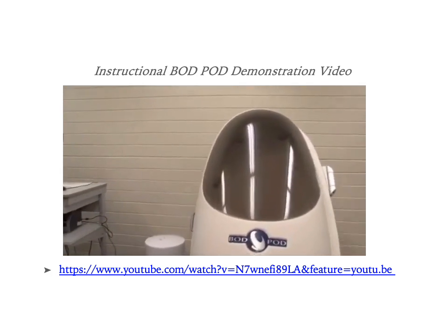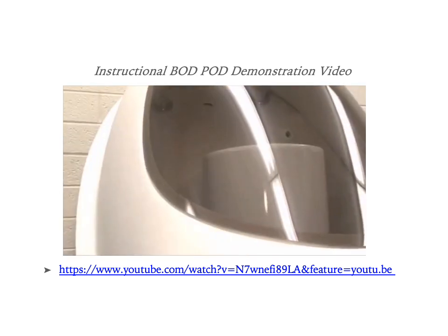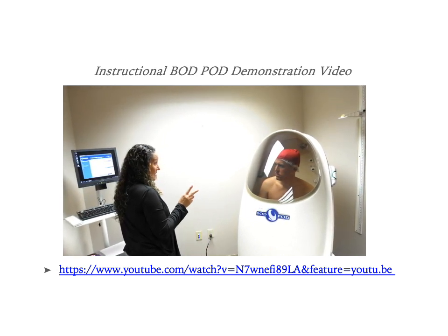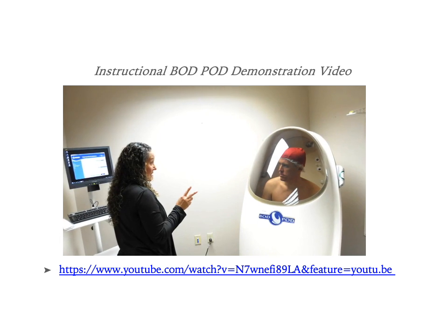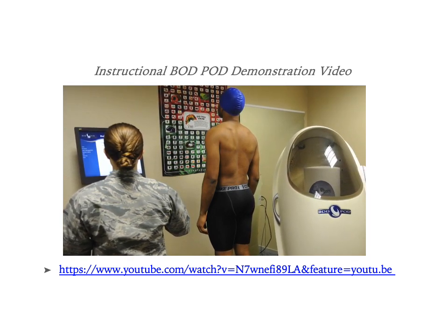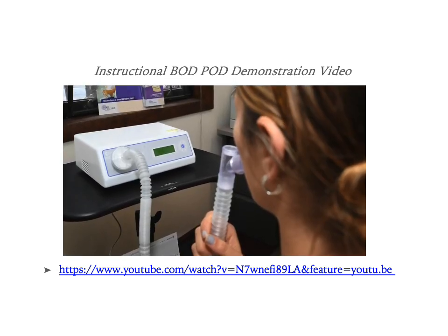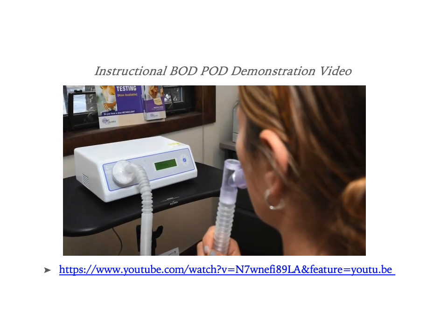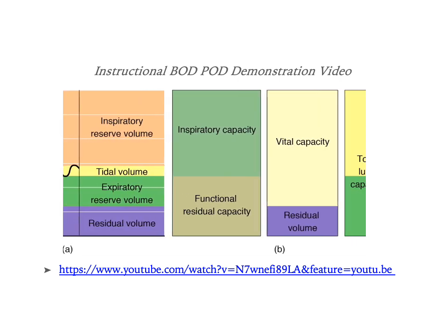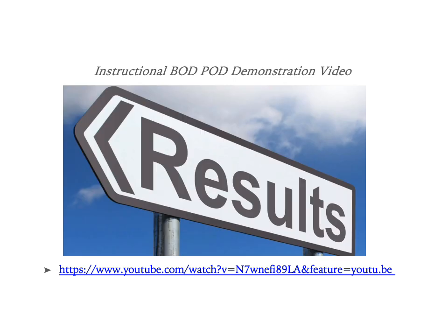Before starting the test, calibrations must be performed. First, the chamber is measured while empty and then with a 50-liter calibration cylinder inside. Two measurements are also done while the patient is inside to assure accuracy. If these measurements do not agree, a third measurement may be taken. Patients are asked to wear tight-fitting clothing or swimsuits as well as swim caps over their hair to minimize air getting trapped. Thoracic gas volume is determined by having the patient breathe into a tube and recording pressure changes — the average volume of air in the lungs during tidal breathing — allowing for more accurate results.